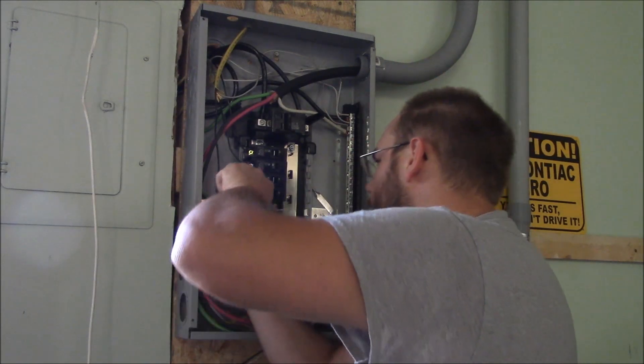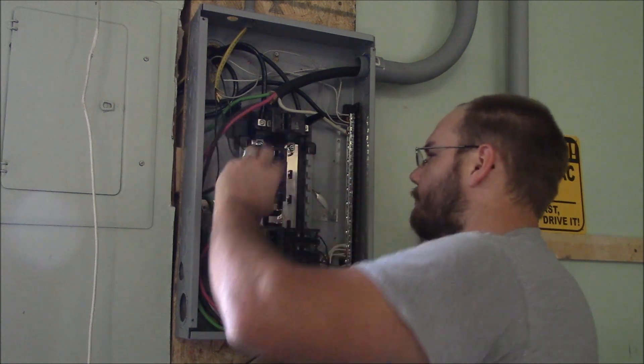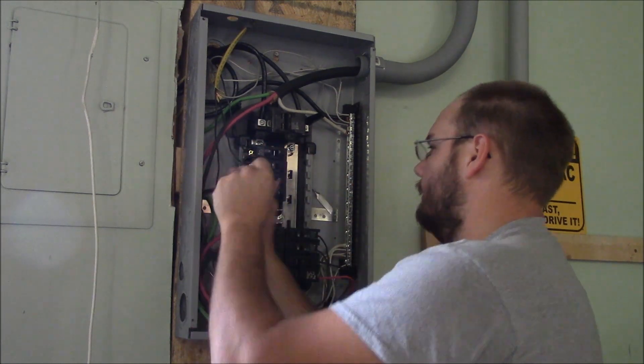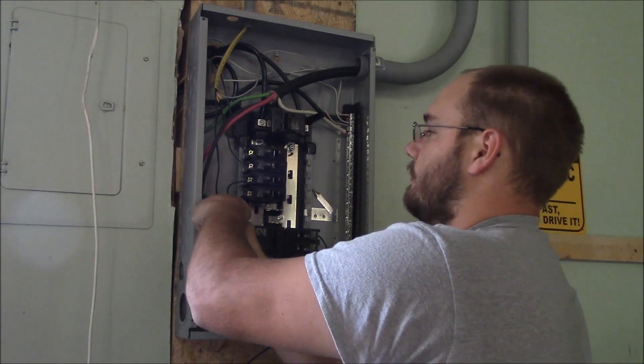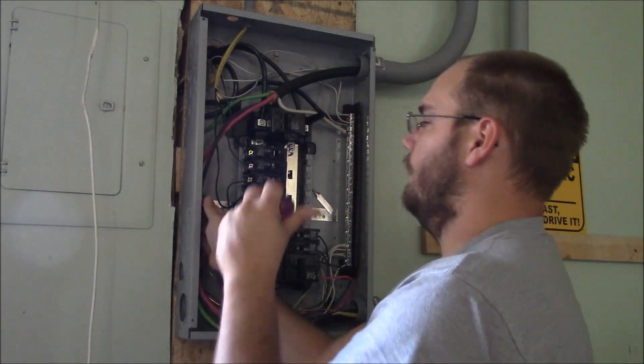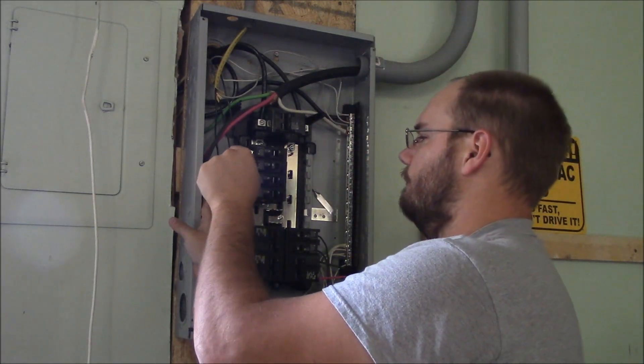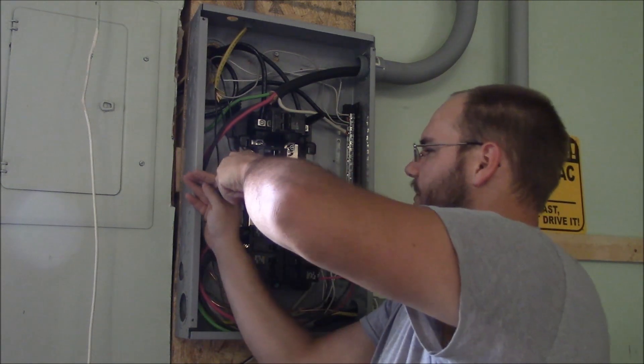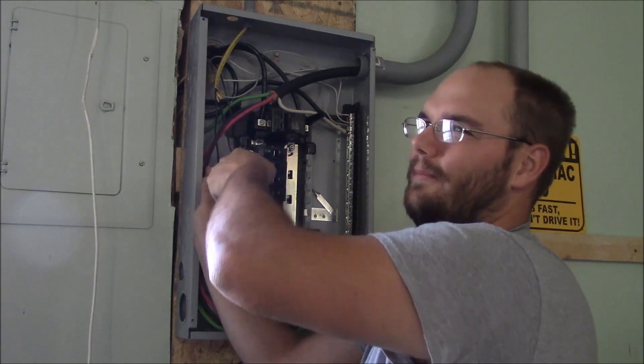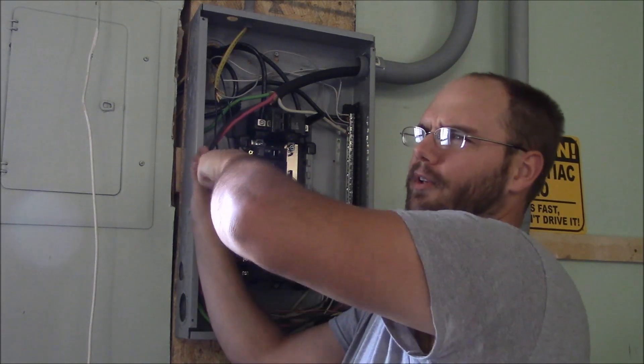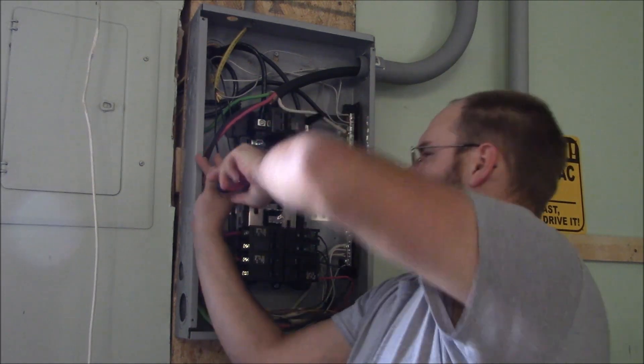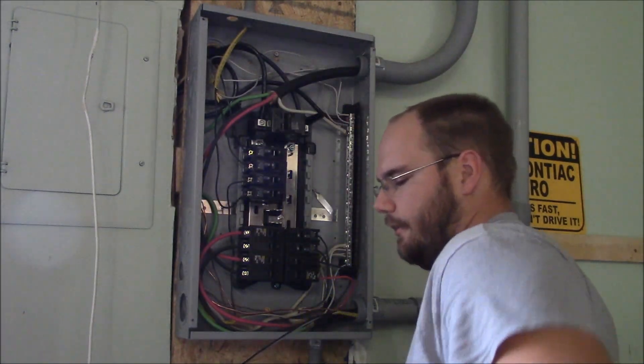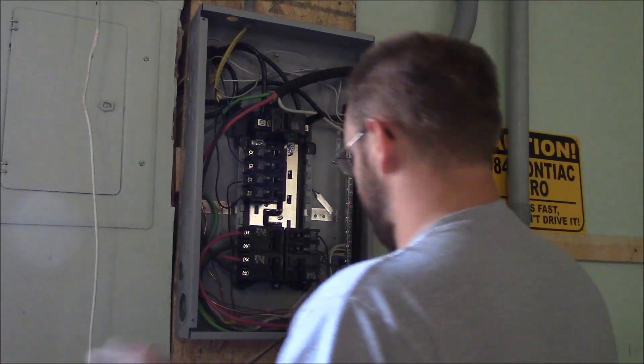You know, flathead screwdriver, generally, and you just pick one of the open slots. And I do say pick one of the open slots—a lot of times there may not be one available. You can double up, but probably shouldn't. I'm gonna say this: you can double up and it'll work, but by code I'm not sure that you're supposed to. You're probably supposed to put in another bus bar. So then you tighten that screw up a little bit. So that's your ground connected.